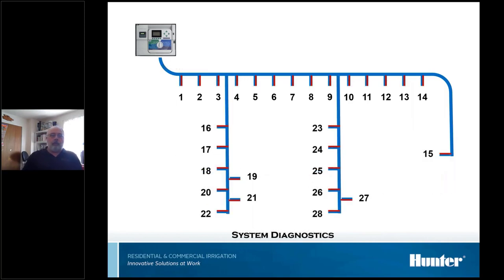So a more realistic system might look like this. Still the same current draw, still the same number of decoders, so the current draw didn't change at the controller any. Obviously, it's going to be different at different points. Like there, we're only seeing that one decoder out on the end. Here, we're seeing those 6. There, it's those 7, so slightly higher, and so on. Those are all the normal readings. That's what you'd expect to see.